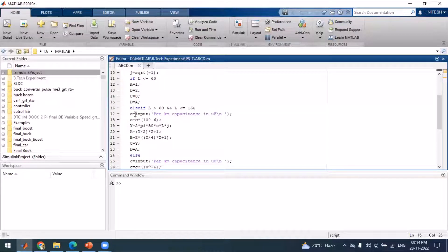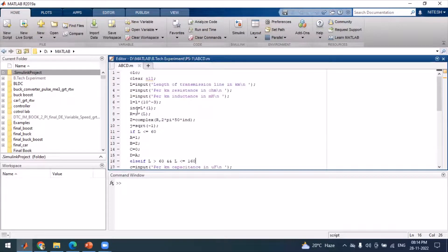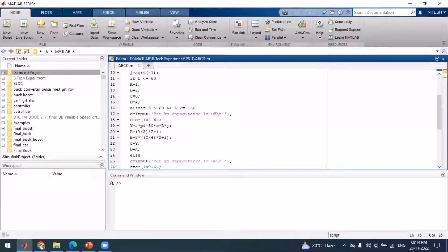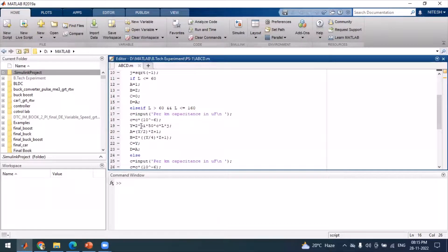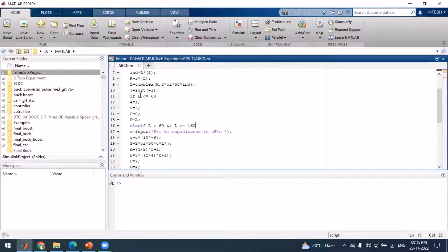If the length of the transmission line is between 60 and 160 kilometers, the code assumes it is a medium transmission line. For the medium transmission line, we take the additional input of capacitance in microfarads and convert it to farads to calculate Y. With Y and Z already computed, we calculate ABCD using the nominal T model formula: A = 1 + YZ/2, and B, C, D are computed similarly.